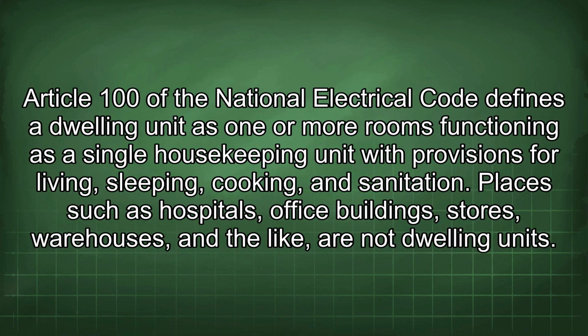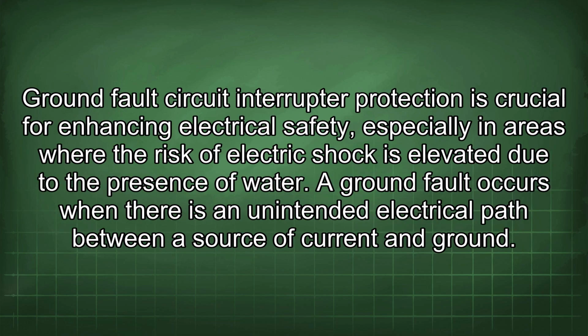Article 100 of the National Electrical Code defines a dwelling unit as one or more rooms functioning as a single housekeeping unit with provisions for living, sleeping, cooking, and sanitation. Places such as hospitals, office buildings, stores, warehouses, and the like are not dwelling units. Ground fault circuit interrupter protection is crucial for enhancing electrical safety, especially in areas where the risk of electric shock is elevated due to the presence of water.